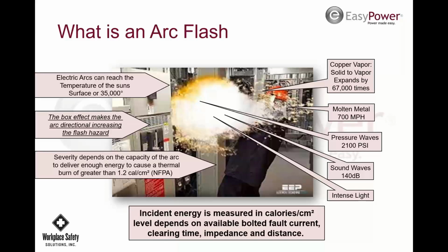And so if that opens up when there's a fault, it opens up so quickly that the ball of fire just might be a little ball of fire that's 3 or 4 inches around. And if I'm working downstream from a breaker and the breaker is 3 cycles, now this was a quarter of a cycle. Now I'm going to go to 3 cycles and it's going to keep on going and going, and now I'm totally engulfed in a ball of fire because it's a breaker that I'm working downstream from versus the fuse. So what I'm working downstream from has a big impact on it.